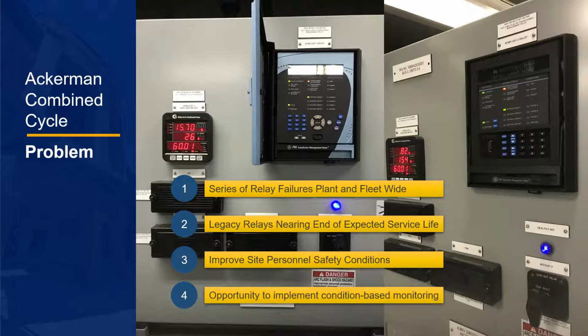Our client in this case was Tennessee Valley Authority, or TVA. TVA had experienced a series of protective relay failures at their Ackerman combined cycle plant, as well as fleet-wide with the use of similar relays. The relays were nearing the end of their expected life cycle, and during the most recent PM activities, the site experienced a handful of failures.